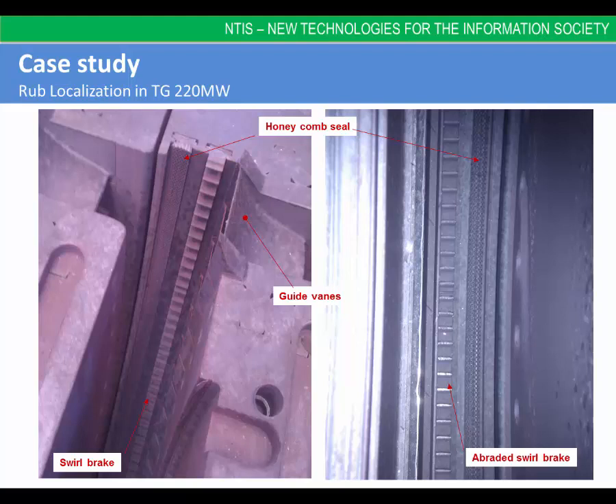In summer of 2012 the high pressure part of the turbine was opened and the estimated places of rubbing were inspected. The results from the axial localization presented above were in full accordance with the results of inspection. Between the fourth and the sixth bladed wheel there were the most significant damages of the seals and abraded swirl brake.